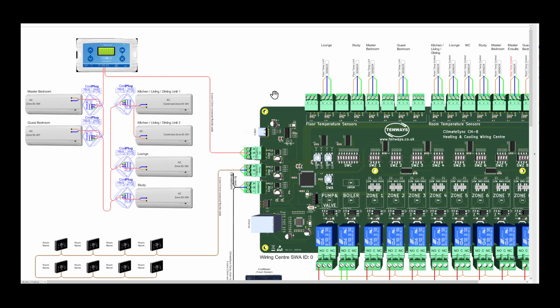If you do it by the wiring center, then instead of daisy chaining the indoor units, you will have a cable from each CoolPlug, 2-core cable or 3-core in some cases, most cases a 2-core, from the CoolPlug to the indoor unit. And then all the CoolPlugs sit by the wiring center. And the advantage of that is that when you position them by the wiring center, when you need to diagnose later, you don't need to go to different indoor units to look at what's happening over there and open the covers. You just have it all by the wiring center.